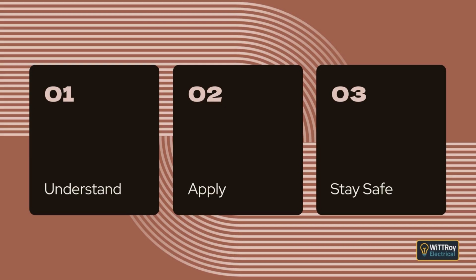Clause 1.5.14, protection against external influences. This clause covers external influences, essentially, what the environment can do to the installation. The installation must be designed so that it can cope with the conditions that can reasonably be expected in the place where it is installed.